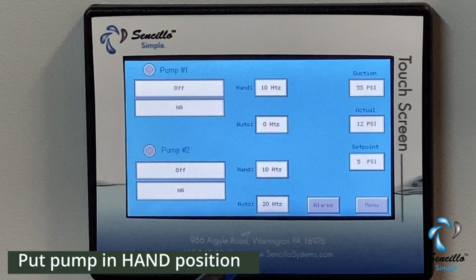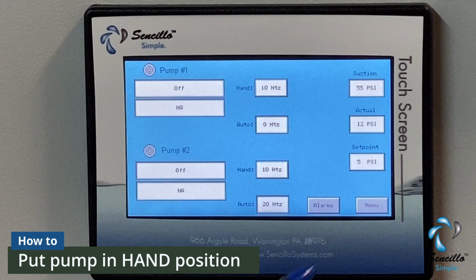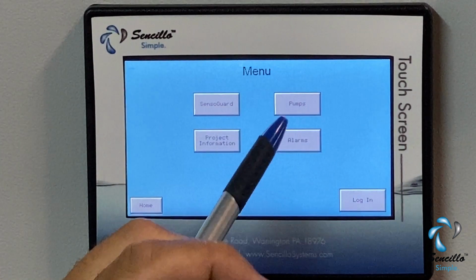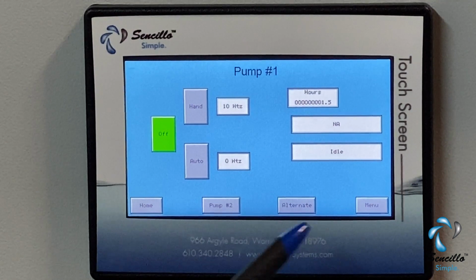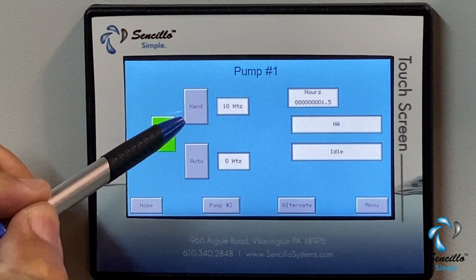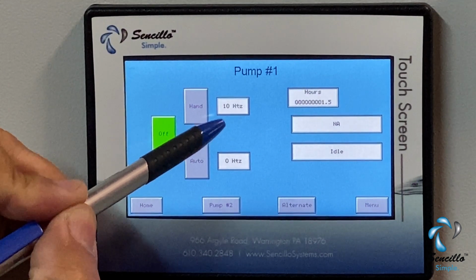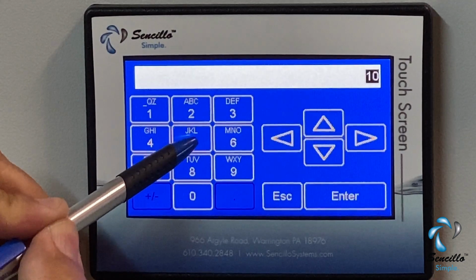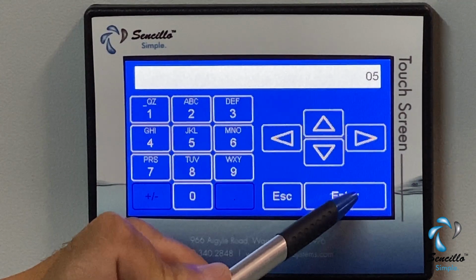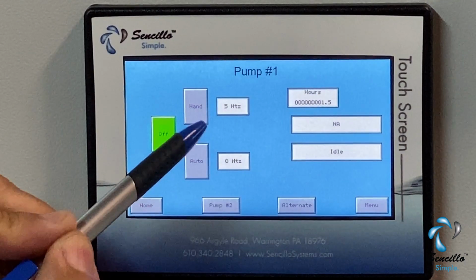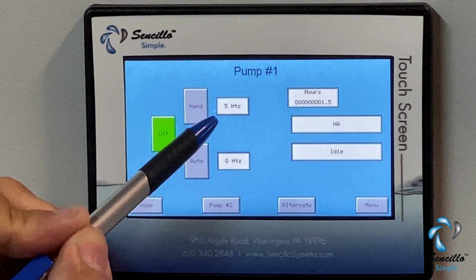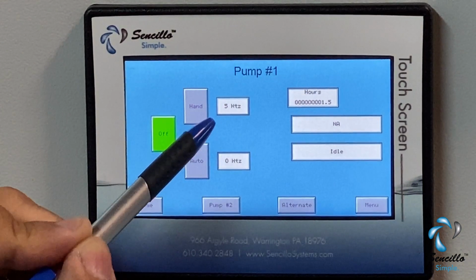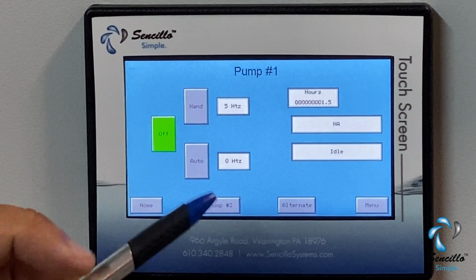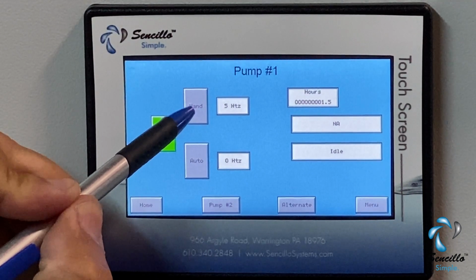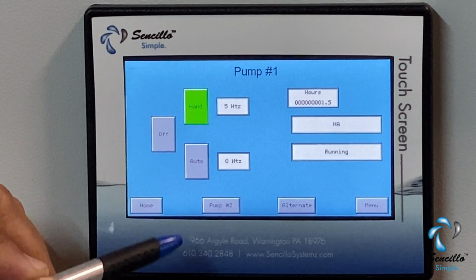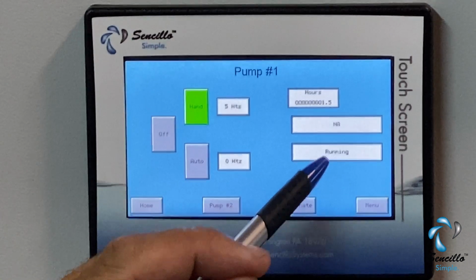Now I'm going to demonstrate how to put a pump in a hand position. We'll go to menu, pumps. Over here next to our hand button, we have hertz. We could type in the speed that we want the pump to run at. In the US market, that goes from 0 to 60 hertz. Once we determined our run speed, we could put the pump in hand position. You now see that the pump is running.